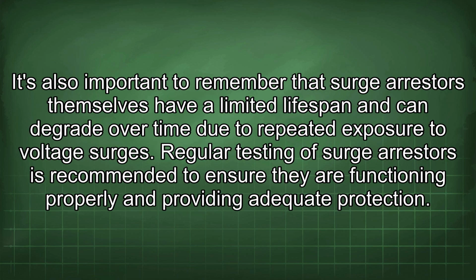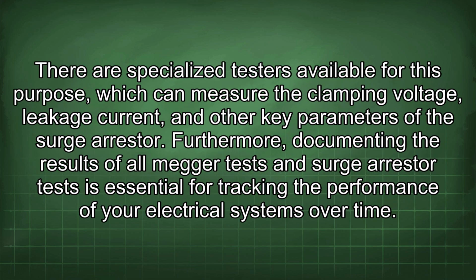It's also important to remember that surge arrestors themselves have a limited lifespan and can degrade over time due to repeated exposure to voltage surges. Regular testing of surge arrestors is recommended to ensure they are functioning properly and providing adequate protection.